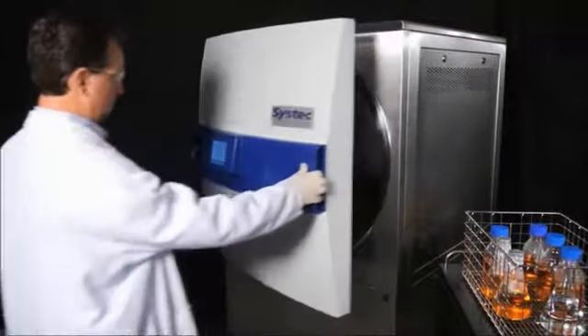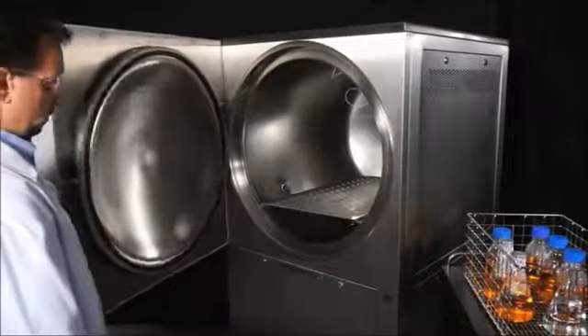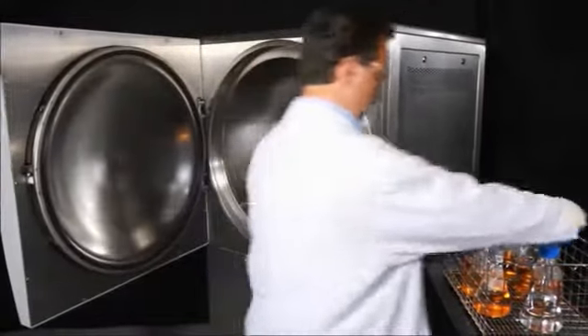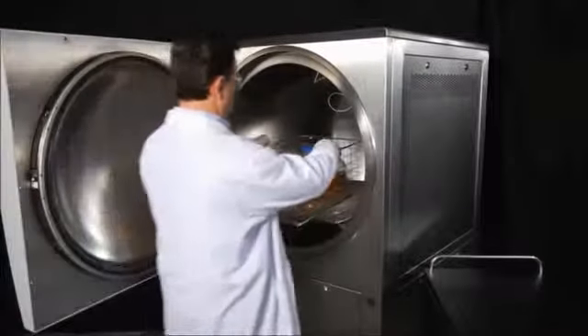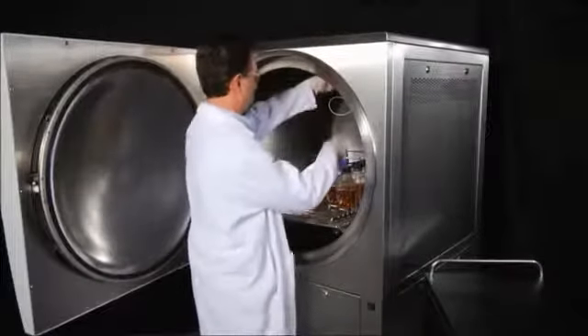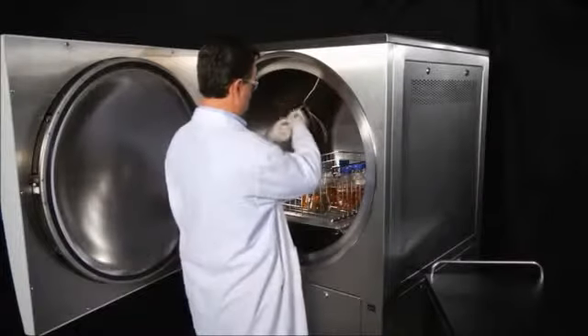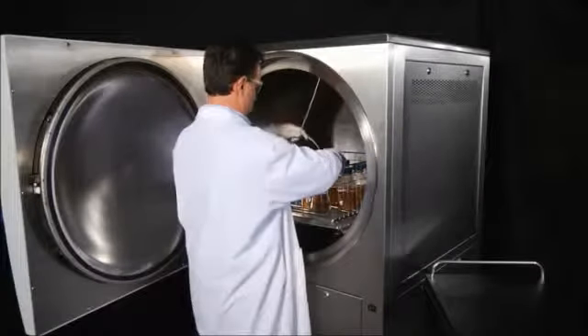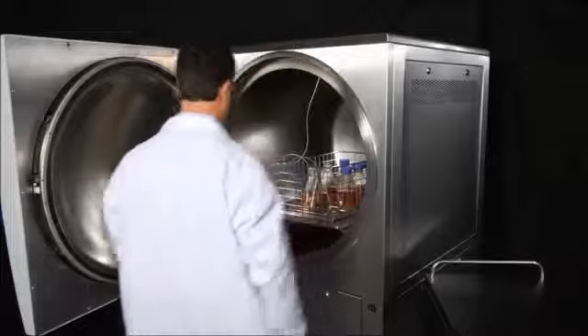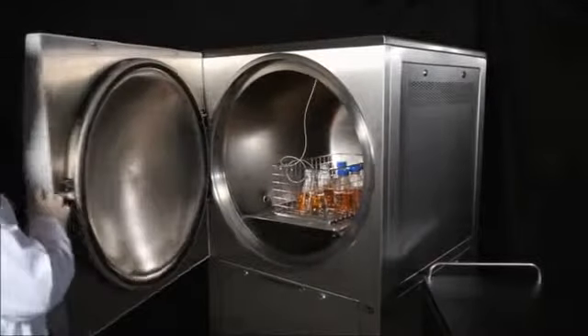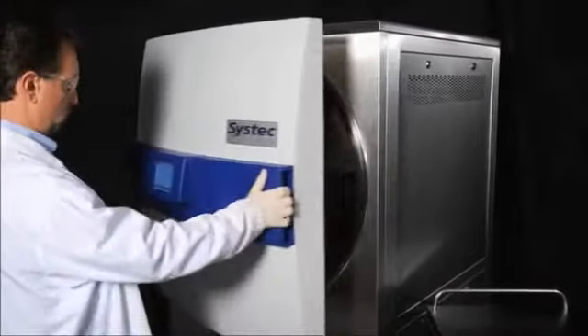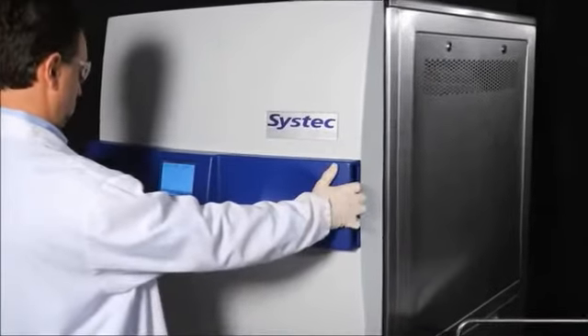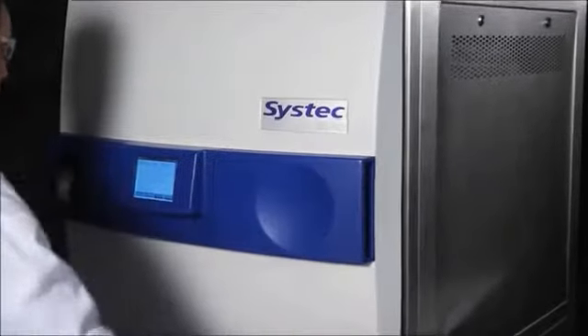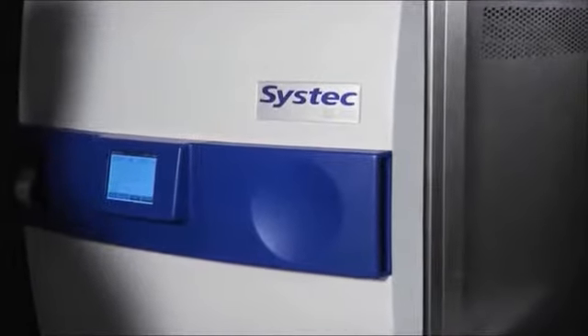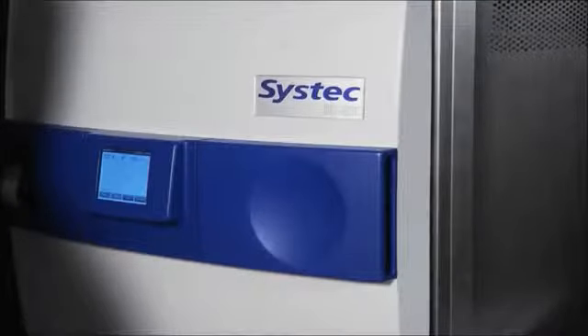The way that Systec autoclaves operate is we condense all of the steam down through the drain, so that way we don't have to have any facility drain connections that are any different than what would be for a normal sink. Also, in condensing the steam down and being able to regulate the way the temperature is controlled, there's no steam release at post-sterilization, so we don't have that big steam burst coming out into the room. So there's a minimal amount of heat that's actually released from the unit post-sterilization.